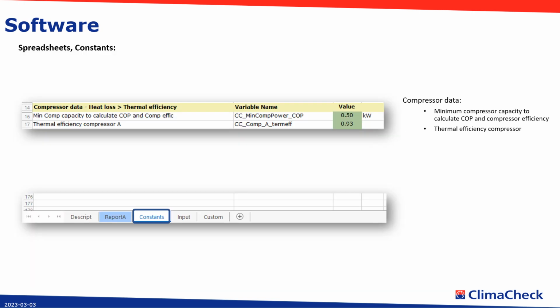In the constant sheet, you can set a constant that defines a minimum compressor capacity when to calculate COP and compressor efficiency. This means that the COP and the compressor efficiency won't be calculated when compressor capacity is below this value. And also you can set the thermal efficiency of the compressor. This is pre-configured to 93% by default, and this is a good and validated value for compressor without any additional cooling.